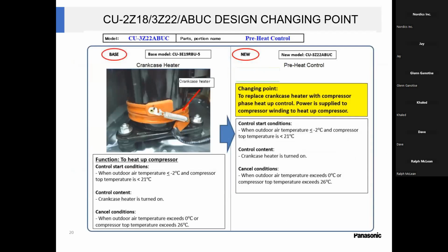As you can see, crankcase heater on the left, that was the old compressor. The new compressor does not have a crankcase heater. Basically, it's going to use the same kind of technology as our single zones. Our single zones use trickling voltage to keep the compressor warm, to keep the oil heated up.